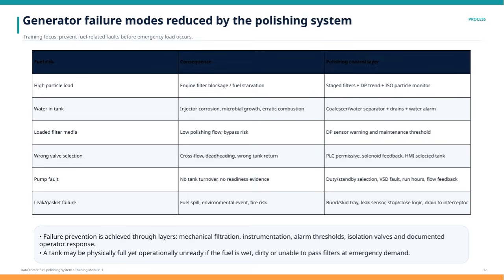Mechanical filtration, sensing instruments, alarm thresholds, isolation valves, and well-documented operator responses all work together to maintain fuel quality and system readiness. Remember, a tank can appear full but still be operationally unready if the fuel is contaminated, wet, or unable to pass through filters during an emergency demand.